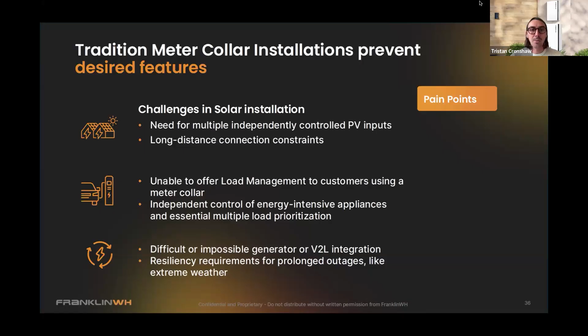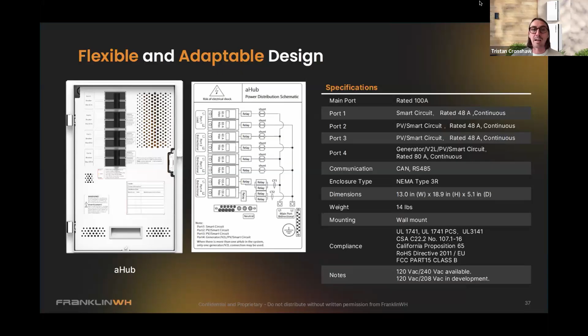The A-Hub is essentially a smart sub panel with four 240-volt breaker spaces, and those breaker spaces can be either 120 or 240. Think of it as like a 4-8 sub panel, 100 amp rated, and each has a CT and relay connected to them. You can configure these breaker spaces in any fashion - it's really just like a sub panel. It would be connected to the main service panel through some type of branch breaker, and then you can work with the customer to decide how to utilize the breakers within the enclosure.